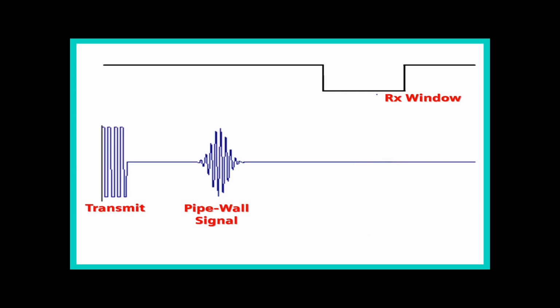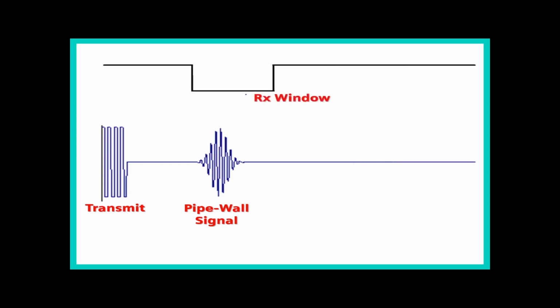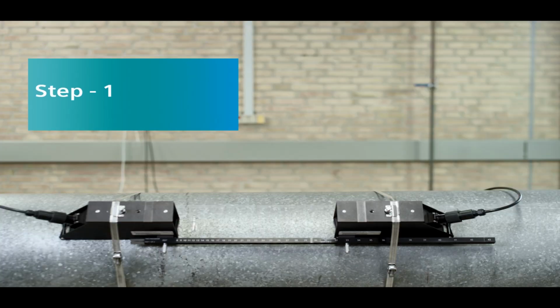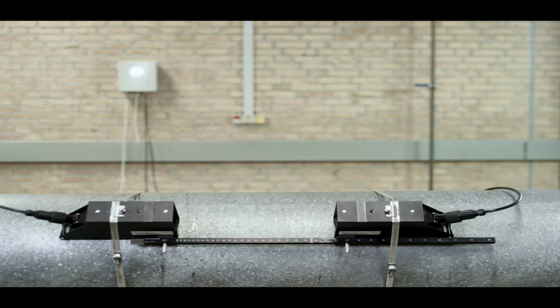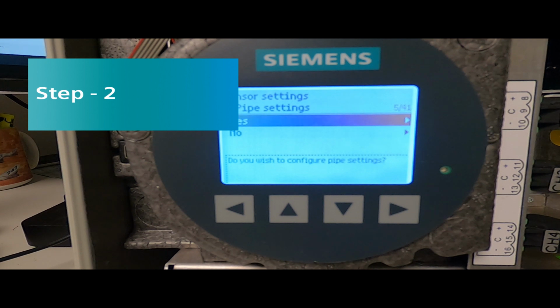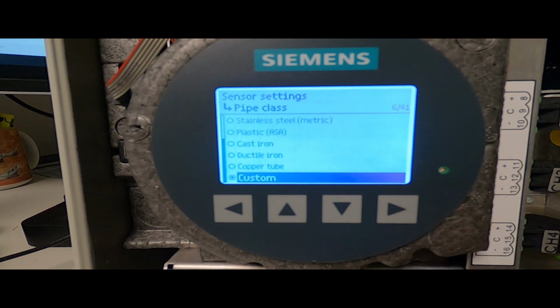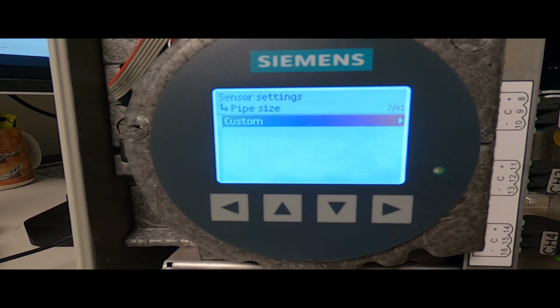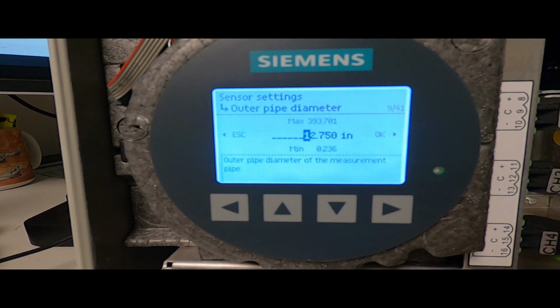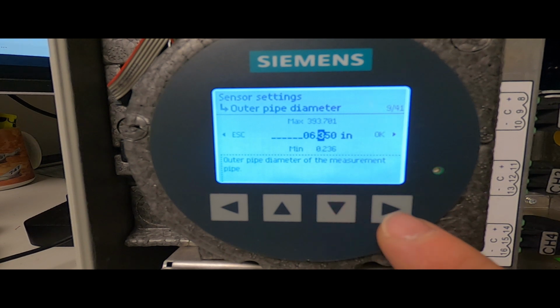To get the meter to see the pipe wall signal, we have to change where it's looking. So step 1, leave your flow sensors exactly where they are currently mounted in reflect mode at the correct spacing for your pipe size. Step 2, and again this is just for liquid applications, change your pipe diameter programming to half the current value. Thus our 12.75 inch outside diameter will now be changed to 6.375 inches.